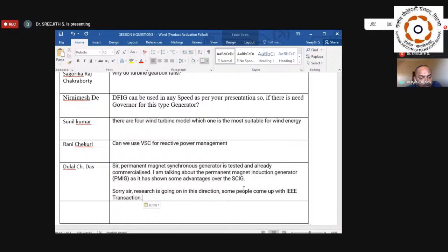Can we use a voltage source converter for reactive power management? Yes, the converters I mentioned, the PWM rectifiers, are voltage source converters. That voltage source converter gives the reactive power required by the squirrel cage machines, as well as reactive power support to the grid. Those are voltage source converters themselves.